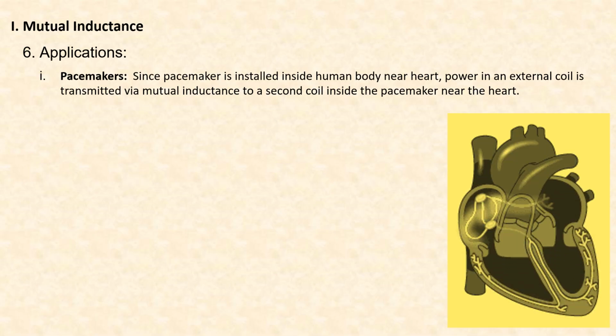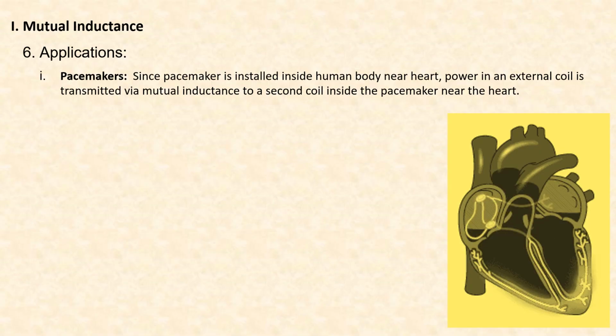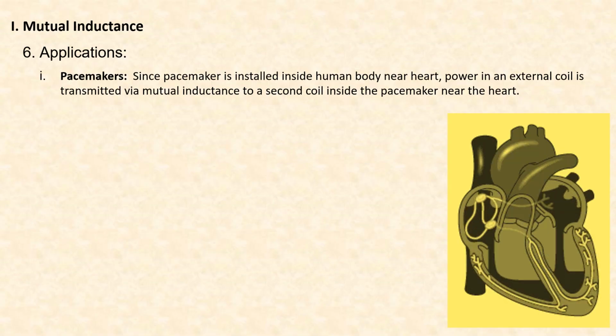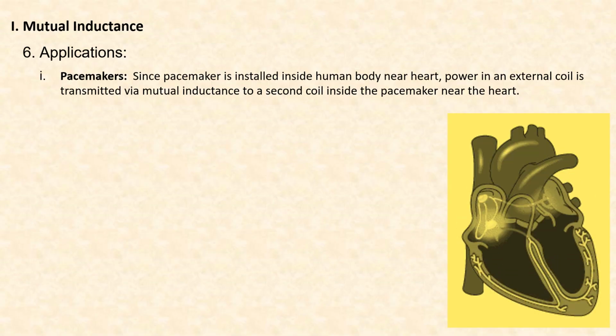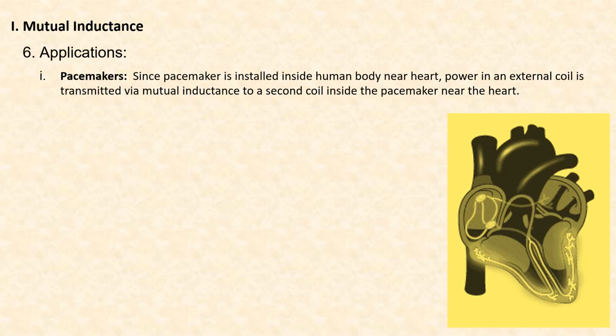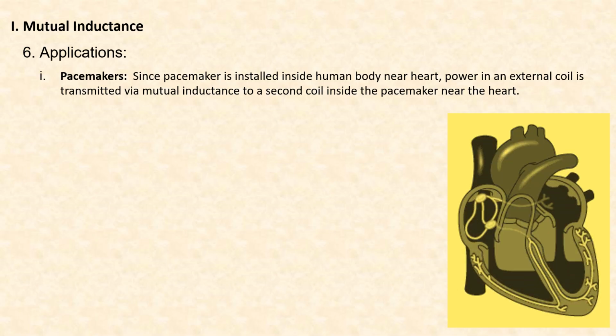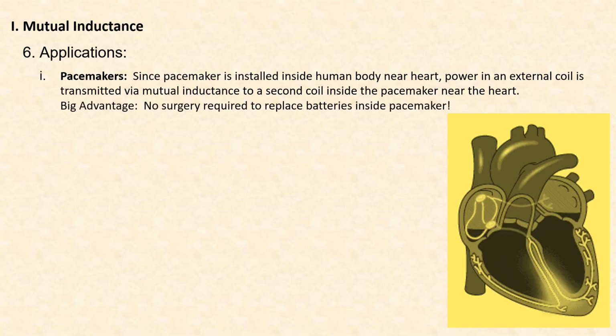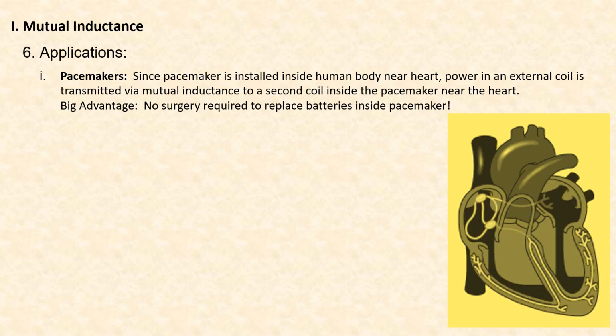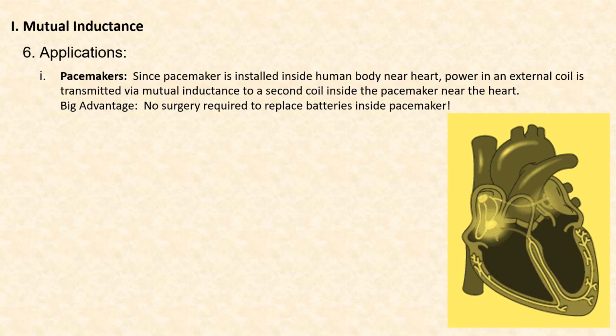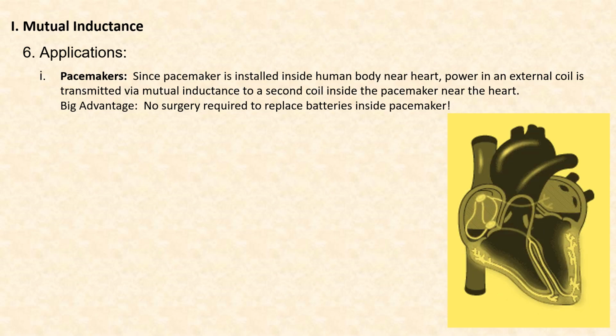You can see here that the changing current in the powered coil outside of the body will transmit a changing magnetic flux through the non-powered coil inside the human body near the heart, and activating that pacemaker when necessary. The big advantage is that no surgery is required to actually replace the batteries inside the pacemaker.